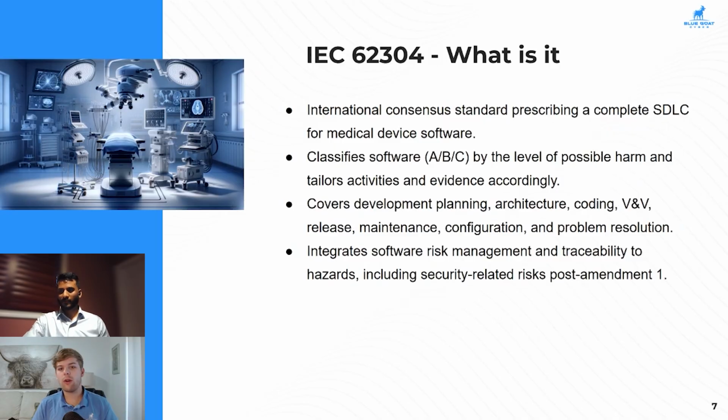If we have a class C or a class 3 device, it's assumed that there's going to be a significant level of risk. This could be maybe an implantable, a high-risk diagnostic machine treating some critical illness, or something where if there's a problem that goes wrong, it could potentially lead to significant harm or even the death of the patient. Naturally, we're going to want to take extra close attention when we're handling a product like this.